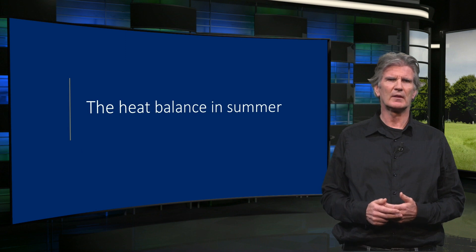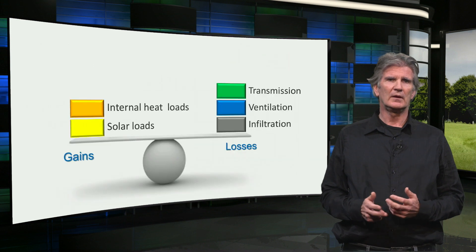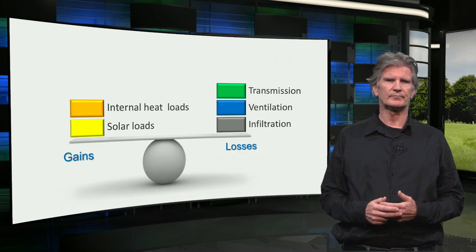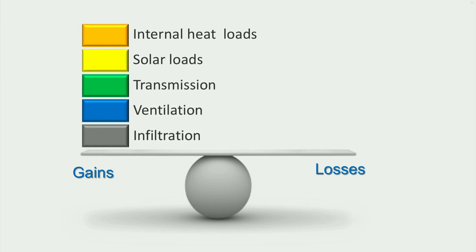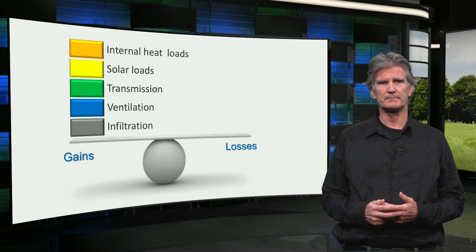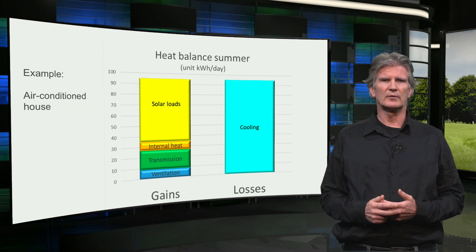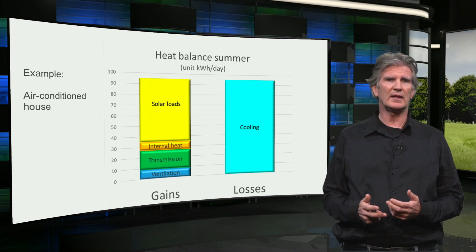What does the heat balance look like on a hot summer's day? In this case the outdoor temperature is higher than the indoor temperature, and there is an air conditioning system to cool the indoor air. The solar loads and the internal loads are still on the gain side, but the transmission, ventilation, and infiltration have also moved to the gain side of the balance, because it is warmer outside than inside. In this case the heat losses only consist of the cooling from the air conditioning.